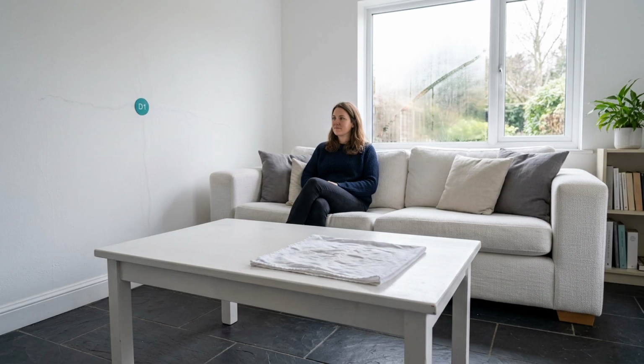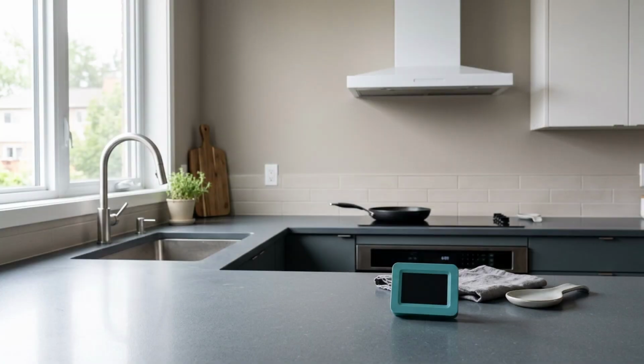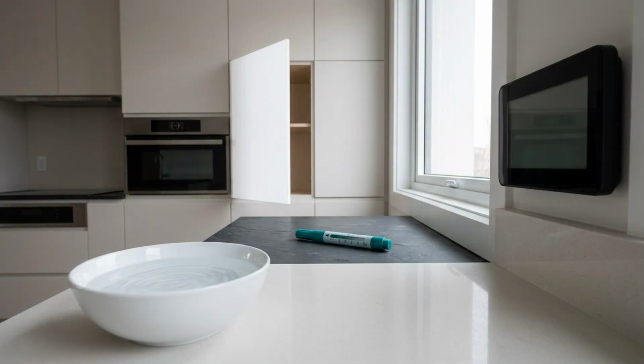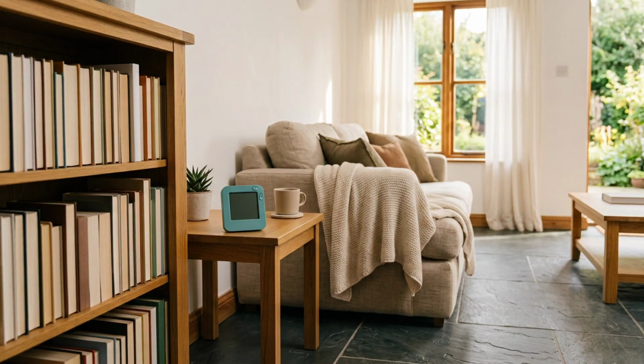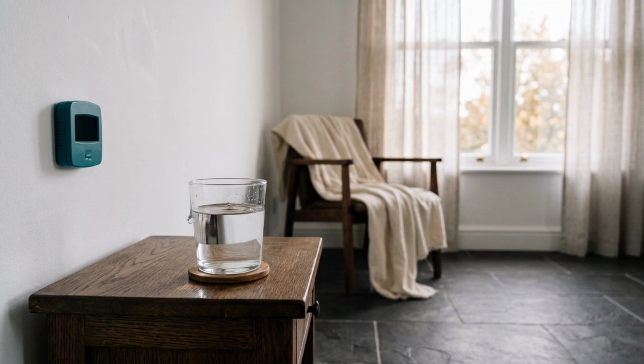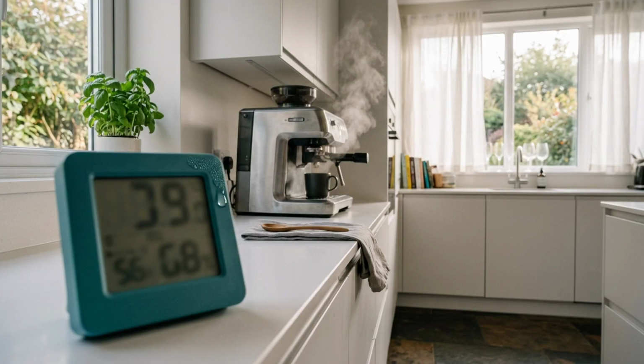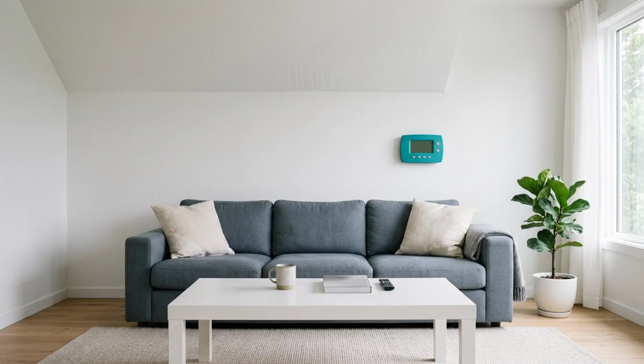A humidity display looks decisive because it gives you one clean number. But relative humidity is not a direct count of water in the air. It compares the moisture present with the amount the air could hold at its current temperature. Change the temperature, and the percentage can change even when no water vapor has been added or removed. That is why 60% is useful, but not a complete diagnosis.